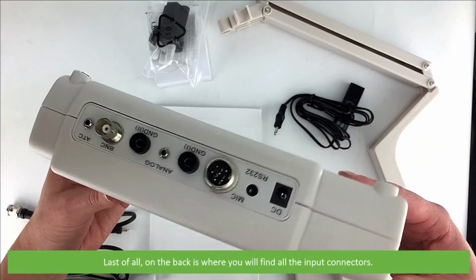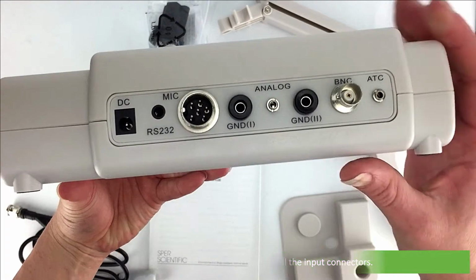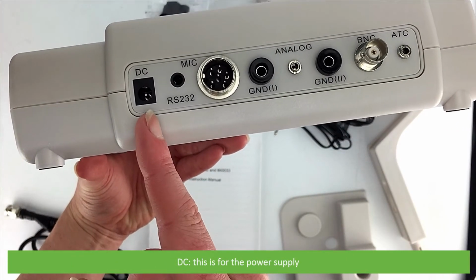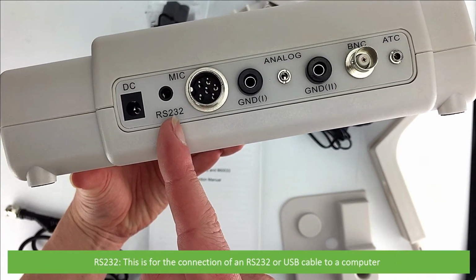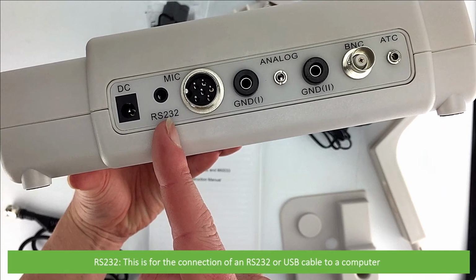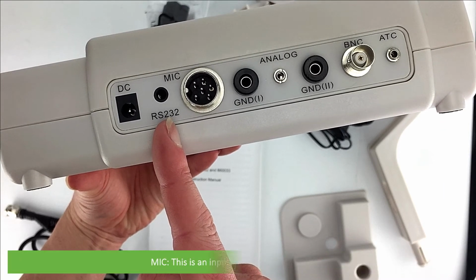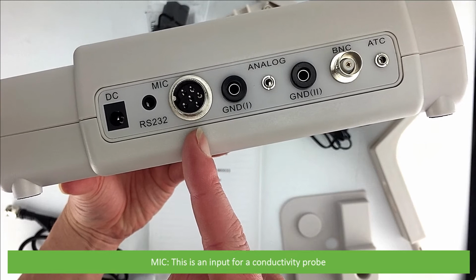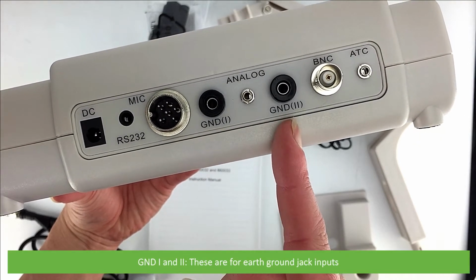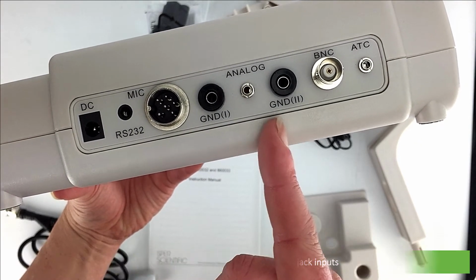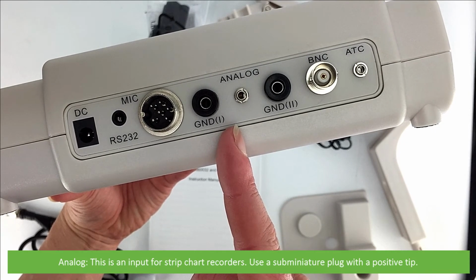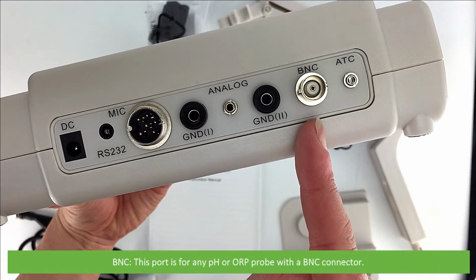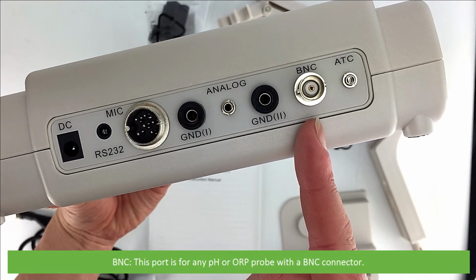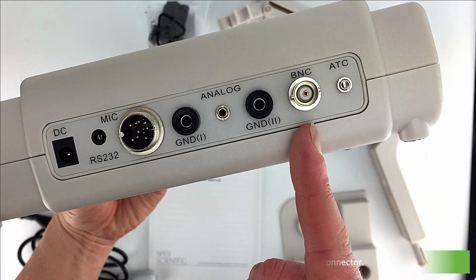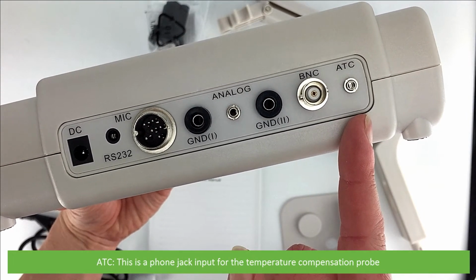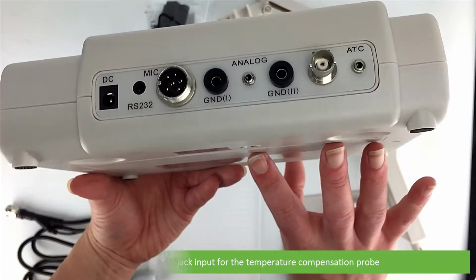Last of all, on the back is where you'll find the input connectors. There's DC for the power supply, RS232, this is for the connection of an RS232 or USB cable to a computer, MIC, this is an input for a conductivity probe, GND 1 and 2, these are for earth ground jack inputs. Analog, this is an input for strip chart recorders. BNC, this port is for any pH or ORP probe with a BNC connector. ATC, this is a phone jack input for the temperature compensation probe.